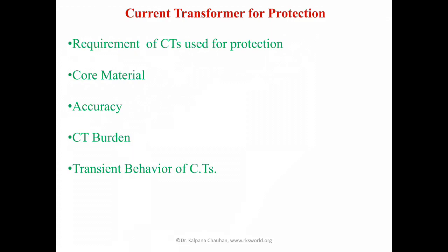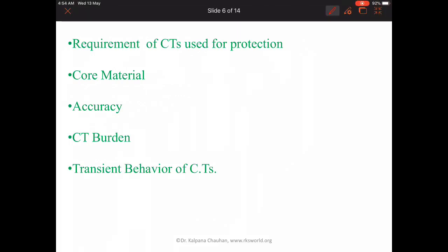If we use the protection system, then there is a requirement of current transformers. Now, first of all, we have to discuss the requirement of CTs for the protection. The requirements of CTs used for protective relays are something different from those of instrument current transformers.